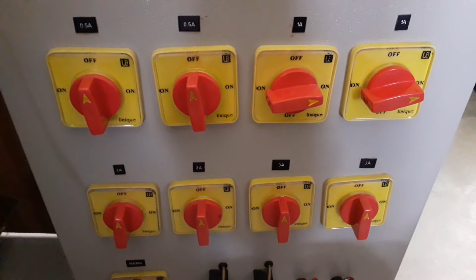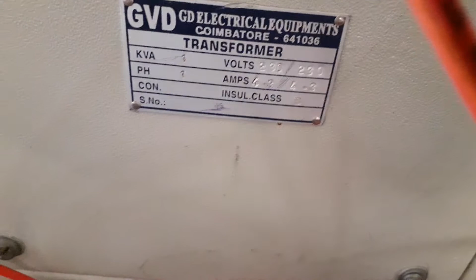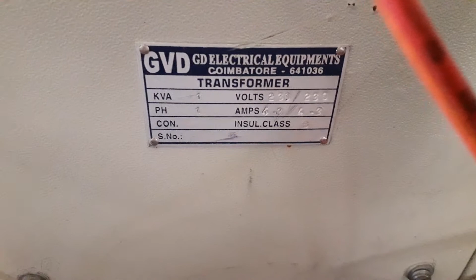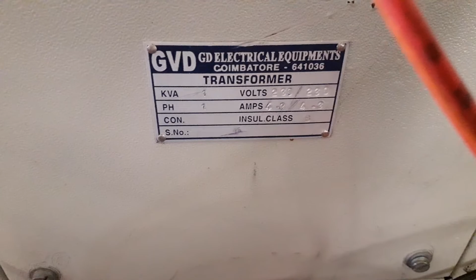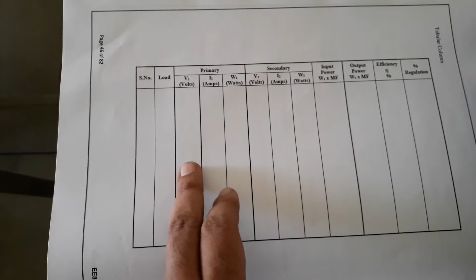Similarly, in this manner you increase the load up to 4 amperes, because the rated current of the transformer is 4.3 amperes, so the load current should not exceed 4.3. We can stop at 4 amperes. For each 0.5 load step, you have to note it down: 0.5, 1 ampere, 1.5, 2, 2.5, 3, 3.5, up to 4. Note down the corresponding primary side voltage, current and watts, and secondary side voltage, current and watts.